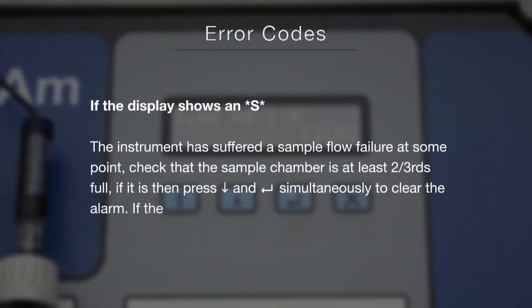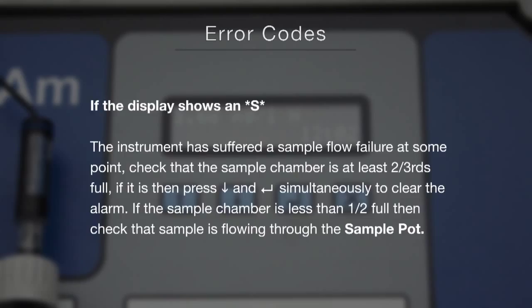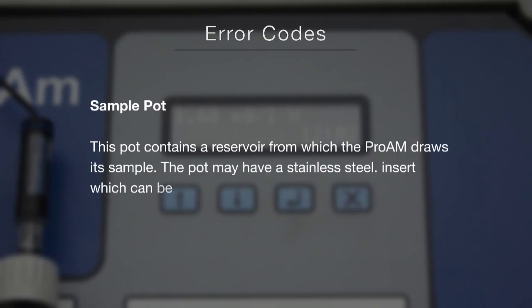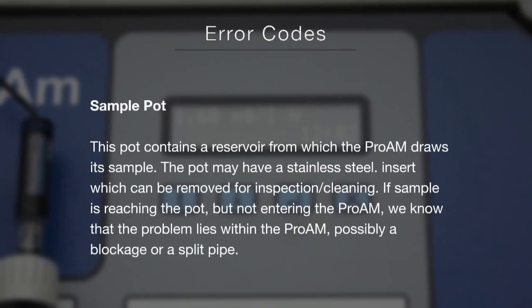If S is on the display, the instrument has suffered a sample flow failure at some point. Check that the sample chamber is at least 2/3 full. If it is, then press the down and enter arrows simultaneously to clear the alarm. If the sample chamber is less than half full, then check that sample is flowing through the sample pot. This pot is a reservoir from which the ProAM draws its sample. The pot may have a stainless steel filter insert which can be removed for inspection and cleaning. If sample is reaching this pot but not entering the ProAM, we know that the problem lies within the ProAM, possibly a blockage or split pipe.